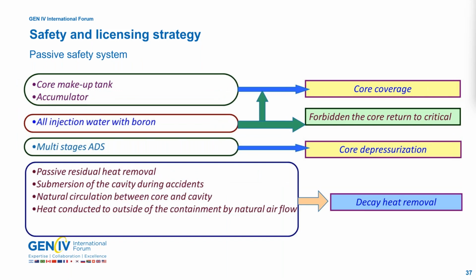The core makeup tank and the accumulator provide the core coverage. All injection water with boron forbids the core returning to critical. Multiple stages of ADS provide the core depressurization. Passive residual heat removal: submersion of the cavity during an accident, natural circulation between core and cavity, and heat conducted to the outside of the containment by natural airflow, providing the decay heat removal from the reactor core to the ultimate heat sink.